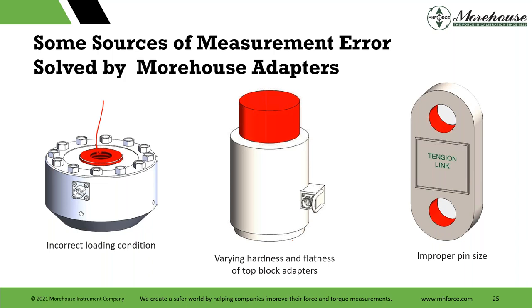Varying hardness and flatness of top blocks. If somebody purchases a system from us, we will supply a top block. That top block will have a specific hardness that will be married to the load cell. When used with that top block, one should not expect the output to change. If one changes blocks intermittently from like a Rockwell 44 to a 52, there's going to be a change in output, probably a 0.3% change.